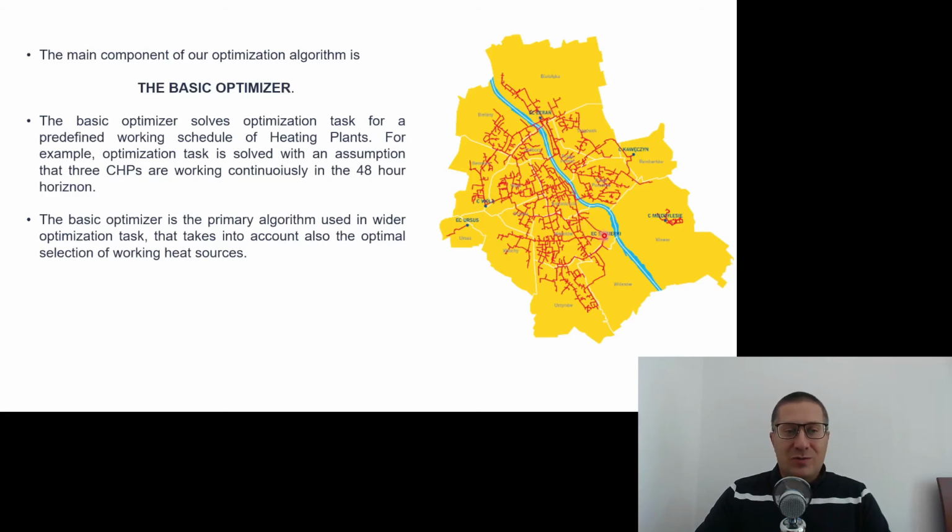Moreover, the quality of the sensor is probably better here, and that is why the machine learning method linked the temperature in this heat source with the temperature in the substation. So it links the temperature in this substation with this heat source, which from the physical point of view is wrong, because it's obvious that this heat source supplies the water to this node.